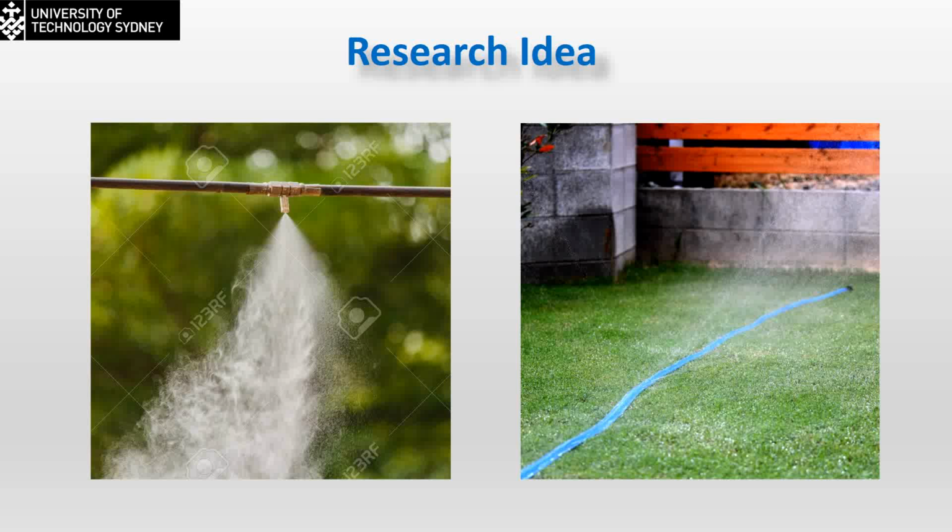And I was walking in the street, I saw that. So I did the same. I got a 4 millimeter diameter tube, punctured it with a needle, and tested it outside. This was giving me the results I would like to have, implemented inside the heat exchanger. For the external sprayer, we have many of those sprayers, high pressure sprayers, which can generate the mist.